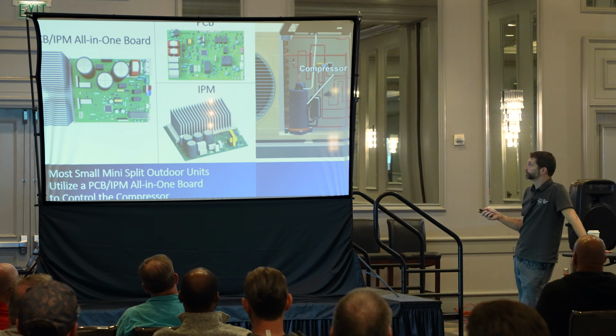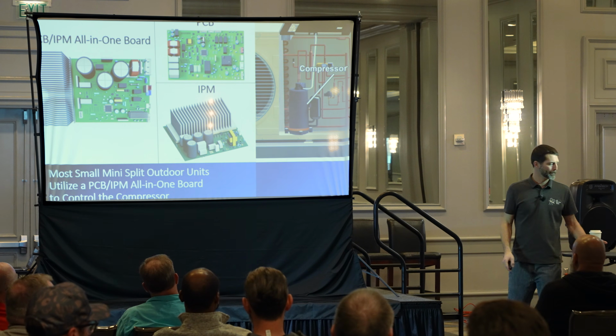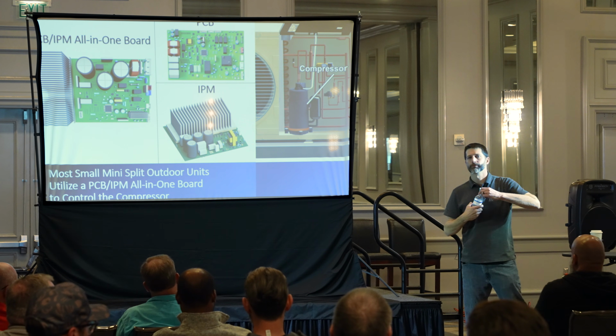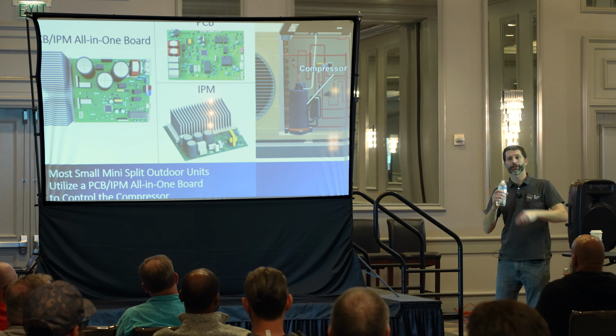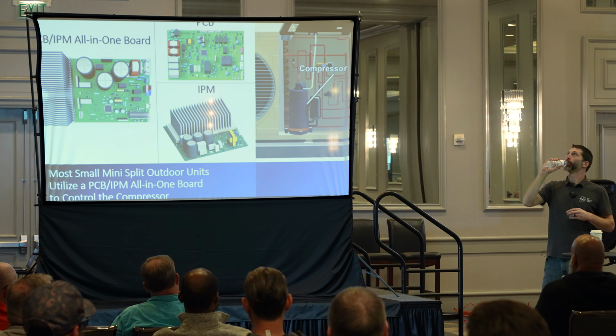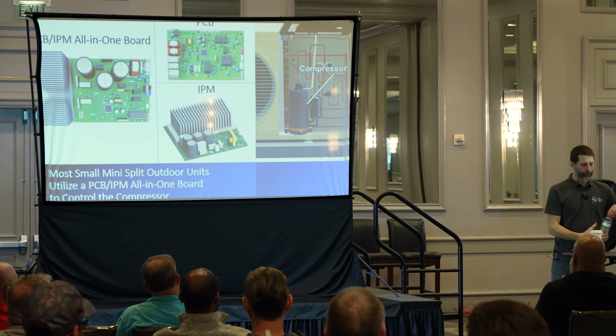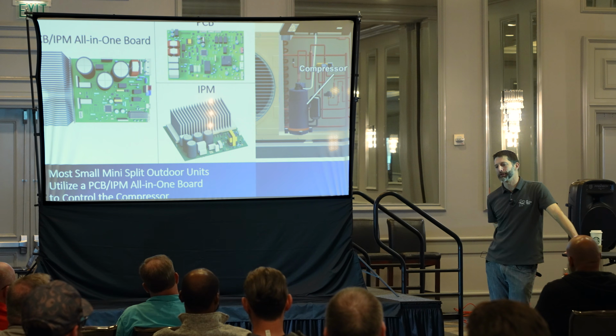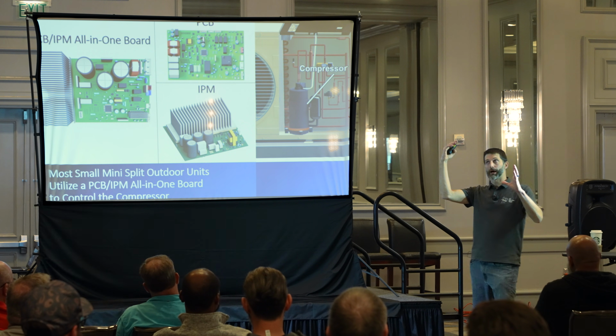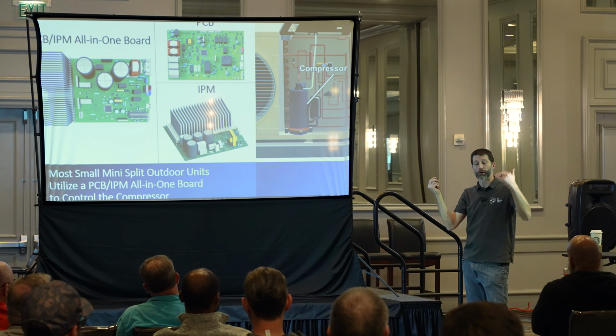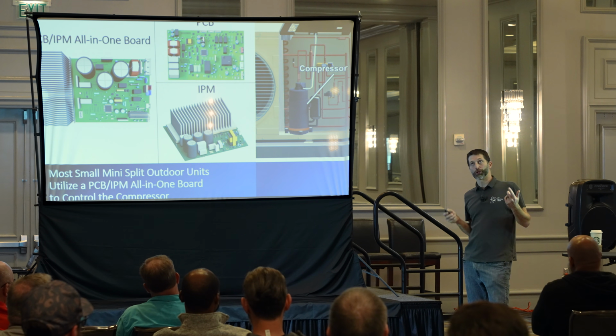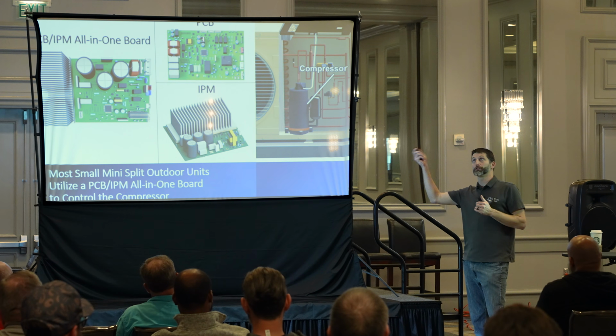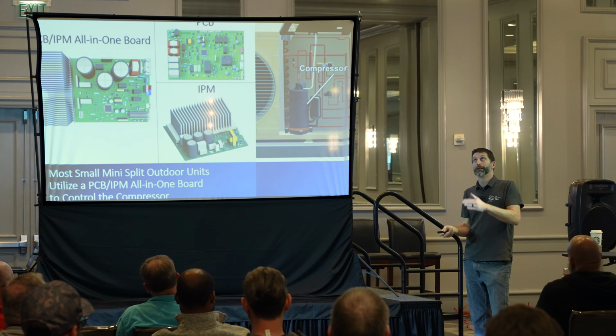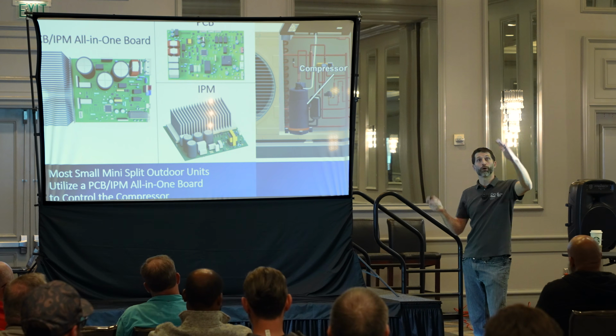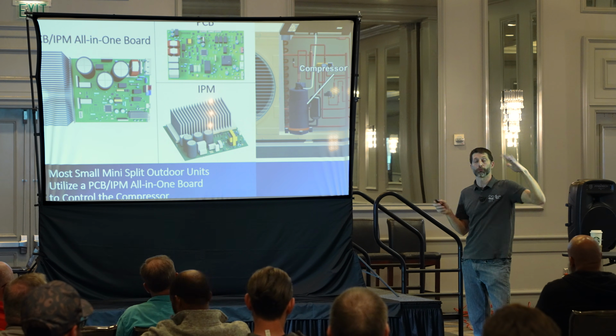Anyway, crazy, right? So what's probably the difference between you pulling the disconnect? I appreciate you saying that because that's where I was trying to get at and I lost it. Okay, so what's worse, going down to 190 volts or cutting it off? You're absolutely right, it's a trade-off. So the voltage monitoring and protection is going to cut off power to the unit while the compressor is running. But the thought is that the failure rate going into the circuit board will be less than if the voltage went down to like 180 volts or some crazy weird thing, or up to 300 volts or whatever it may be.